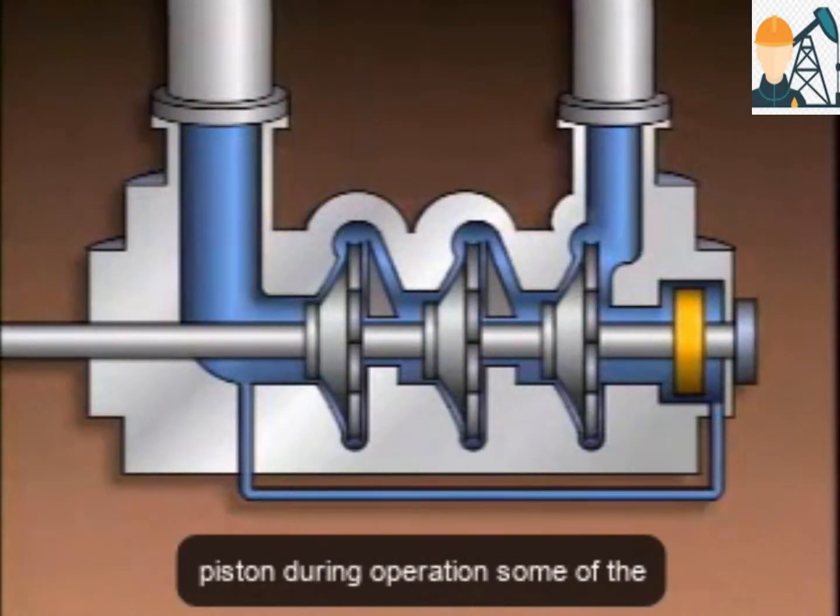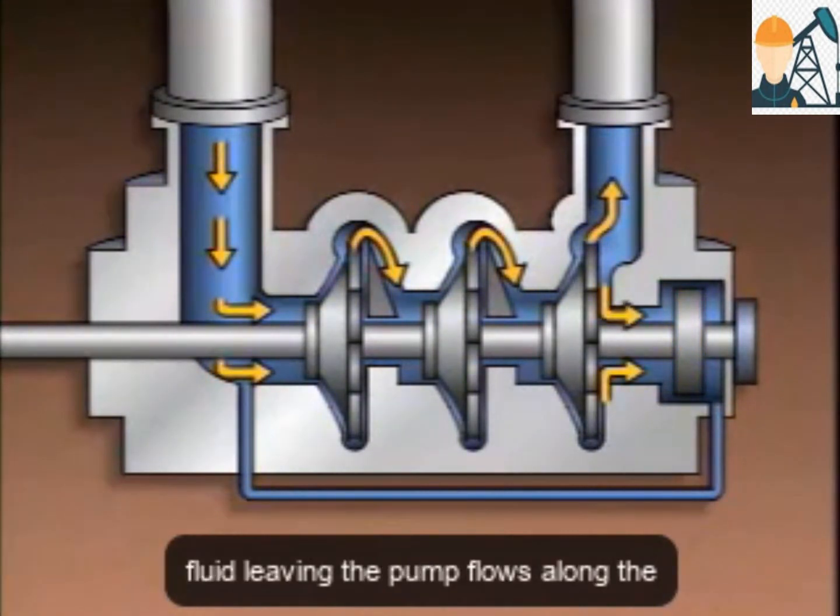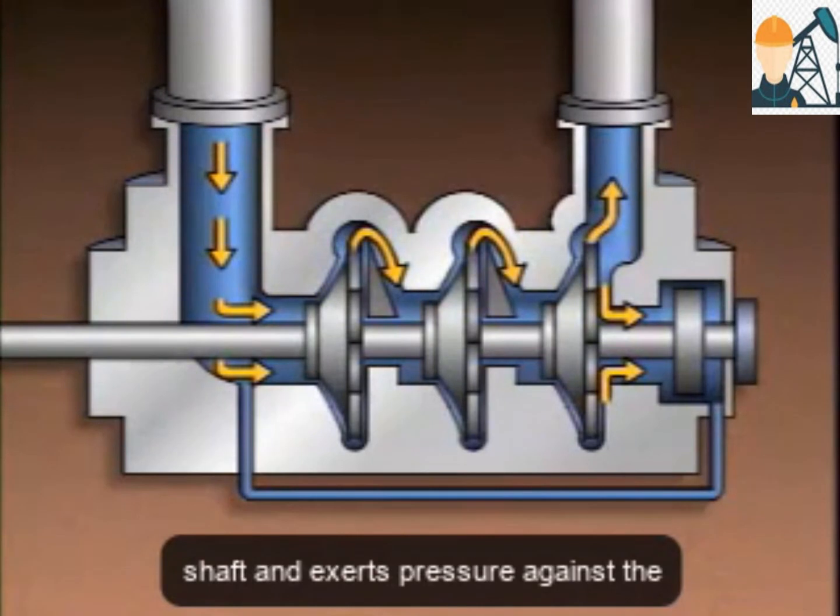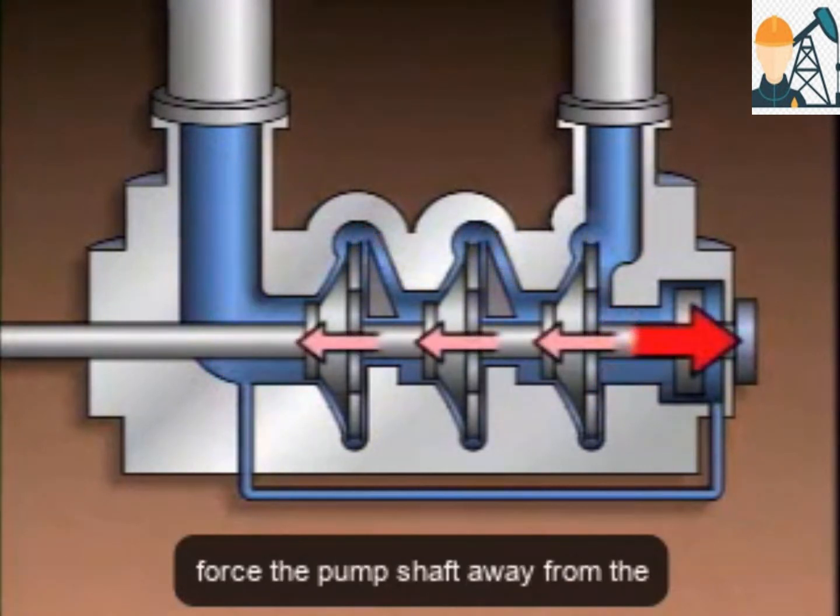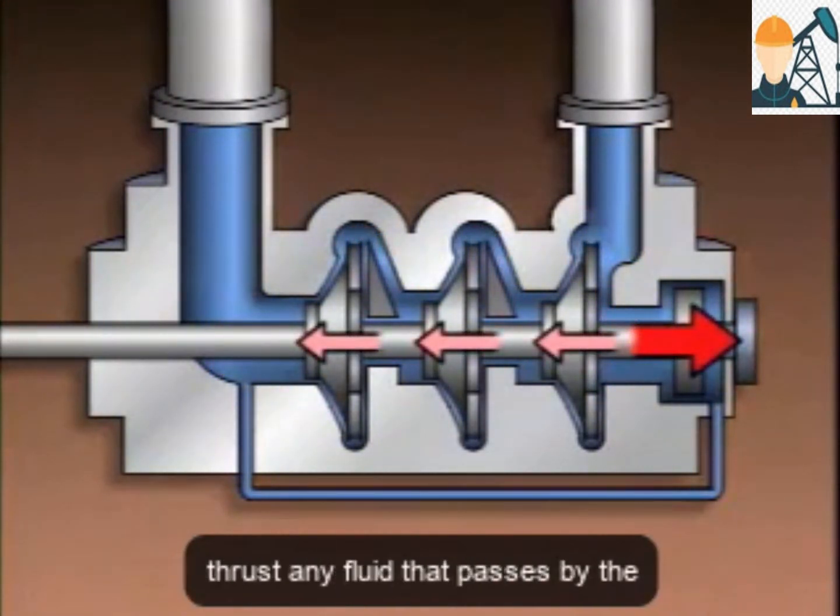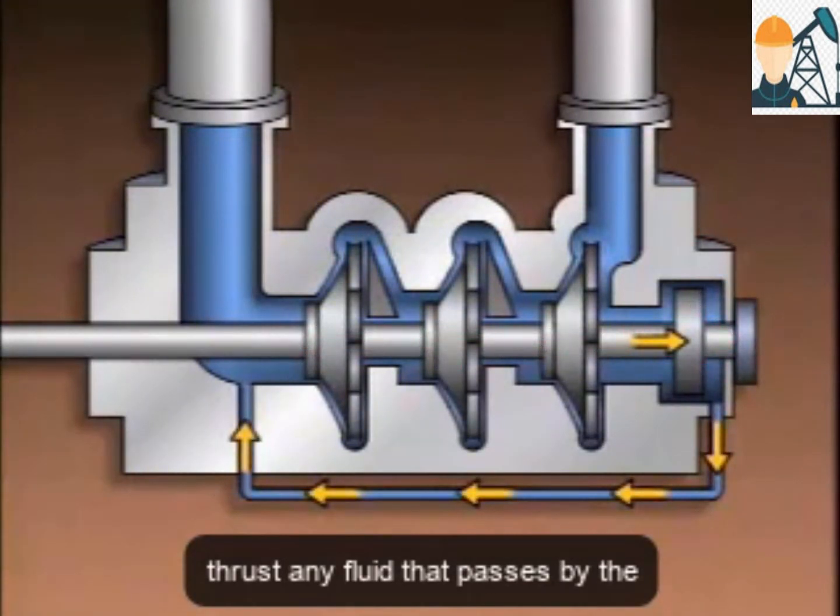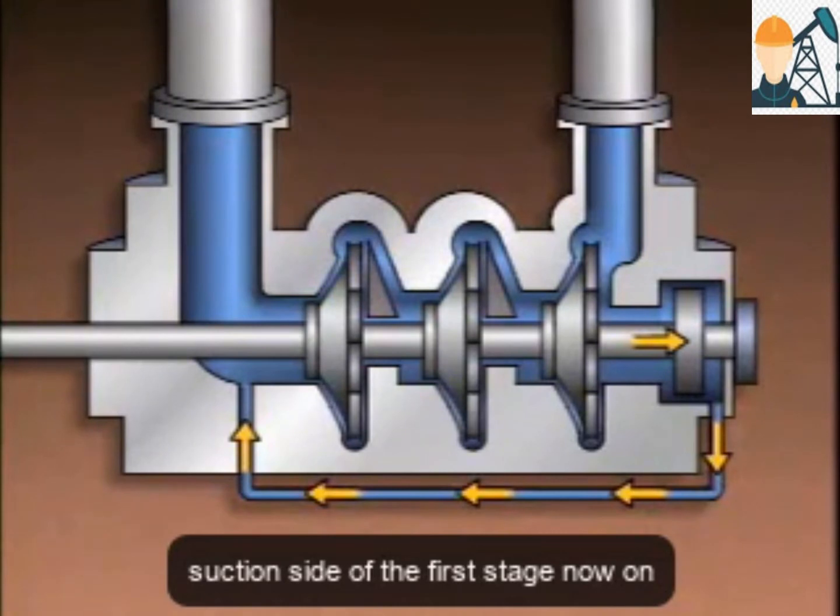This pump has a balance piston. During operation, some of the fluid leaving the pump flows along the shaft and exerts pressure against the balance piston. That pressure tends to force the pump shaft away from the suction eyes and reduces the total thrust. Any fluid that passes by the balance piston is returned to the suction side of the first stage.